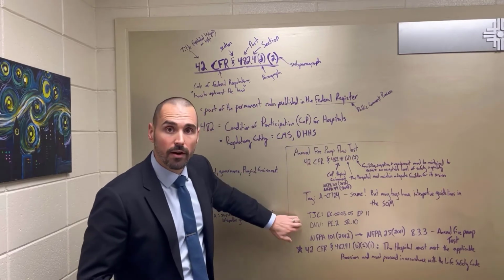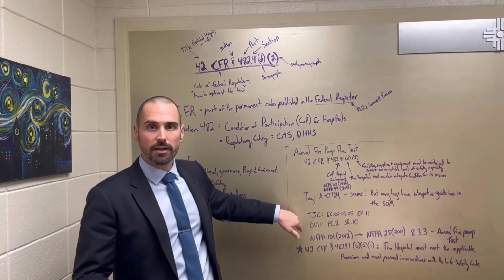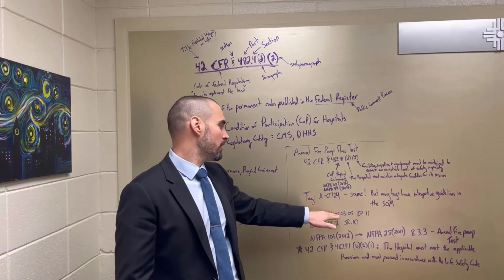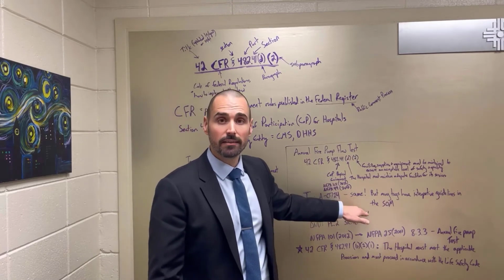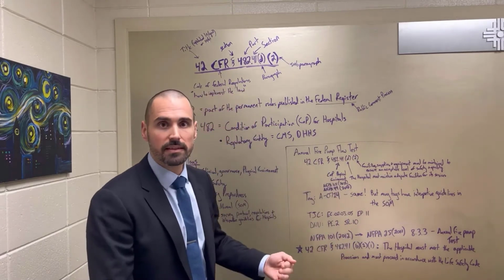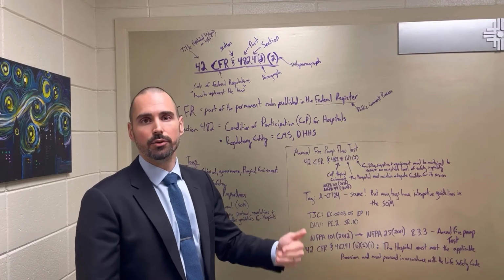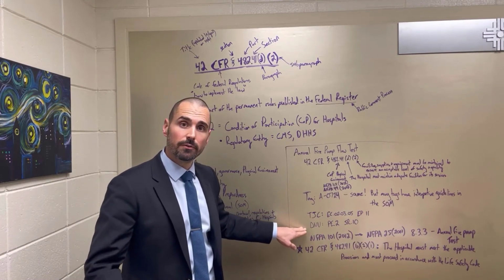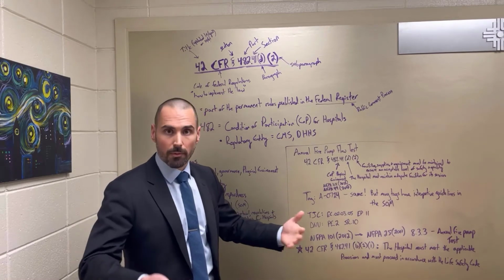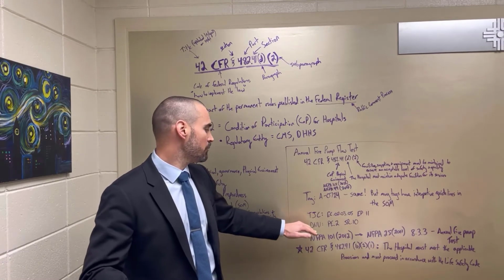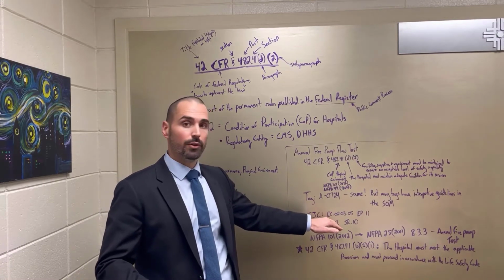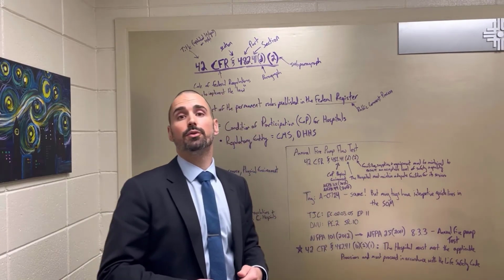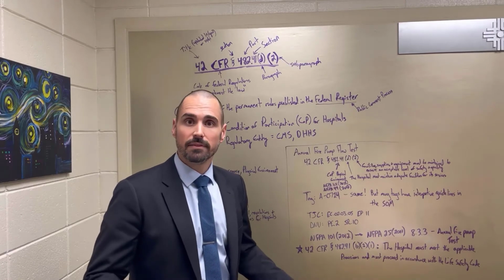And then you have accrediting organizations. I've got a few here just to talk through. Joint Commission, which says EC.02.03.05, EP 11. And it's very specific on theirs. It says you have to, every 12 months, do an annual flow of your fire pump. And then you have DNV, which is a little bit less prescriptive, because it's just a different model of how they operate. They have Physical Environment 2, which is the guideline, SR.10, and it just says that you have to test and inspect your life safety systems, right?